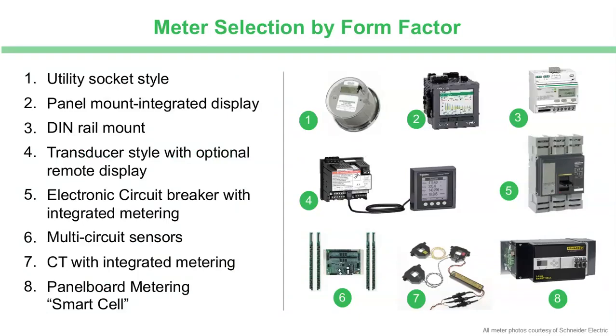The other quick criteria that you maybe want to be aware of is that meters do come in different form factors. Quickly going through these, you see number one looks a lot like the meter on the building or maybe on your home, and that's an under-glass utility style meter. Other styles of meters are shown, whether they are mounted on a door, mounted inside the enclosure, or if the display is remote. But then we get to number 5 there, and that's the idea that we can incorporate intelligence within power distribution equipment and power equipment in general.